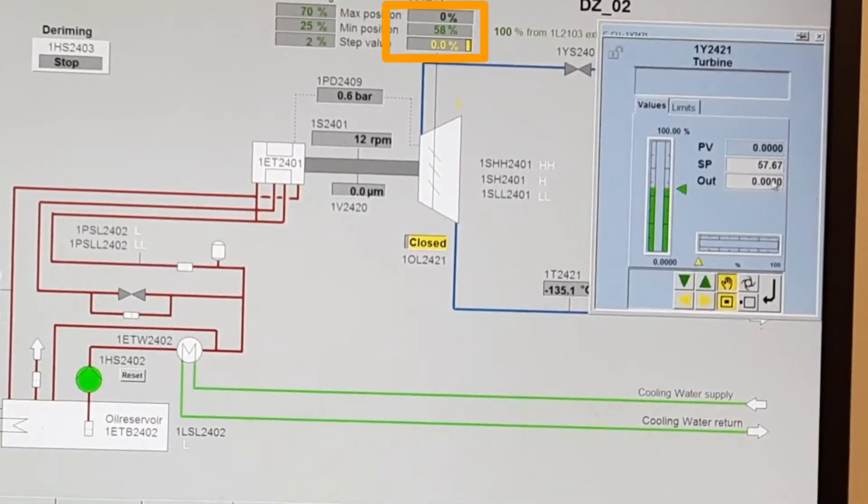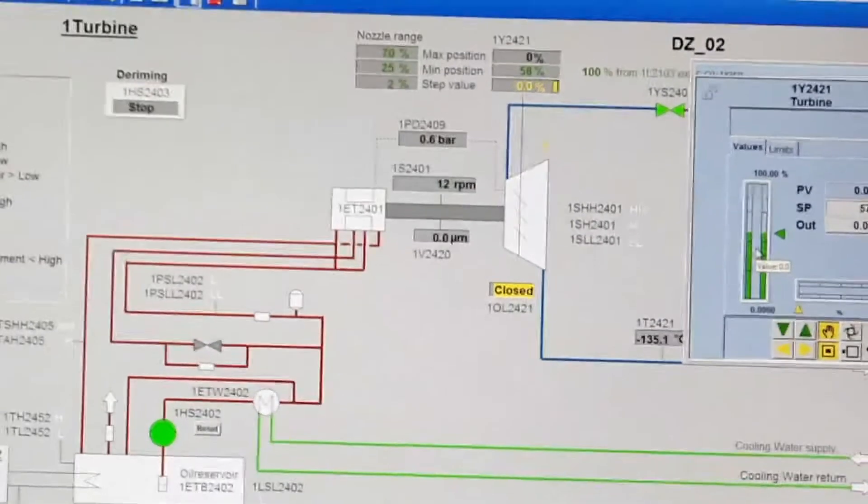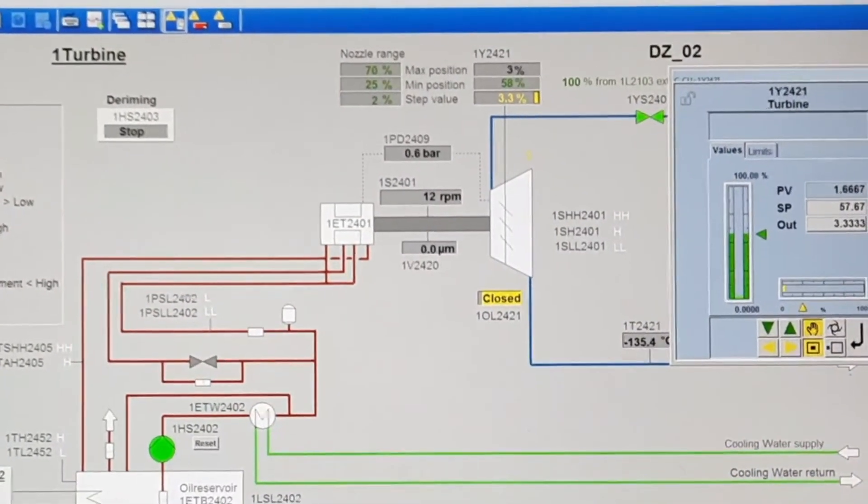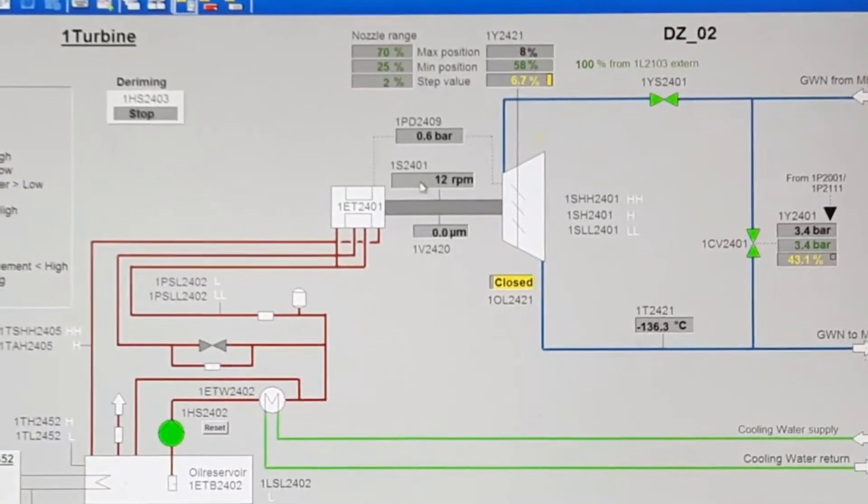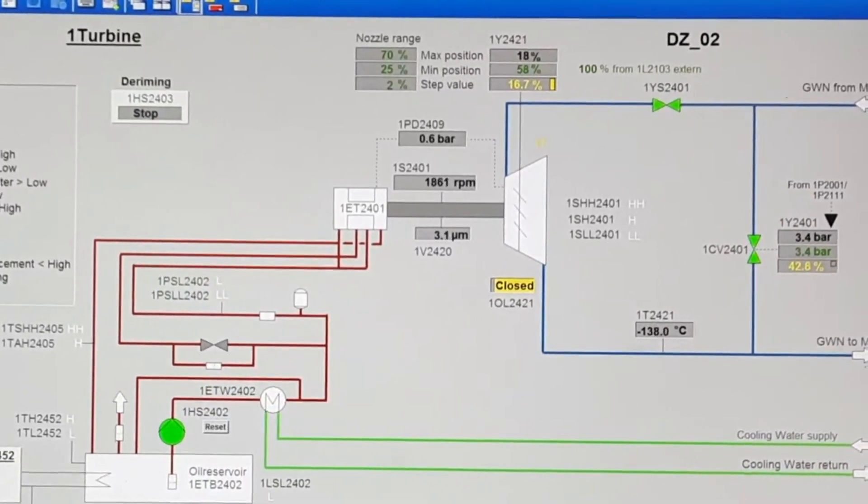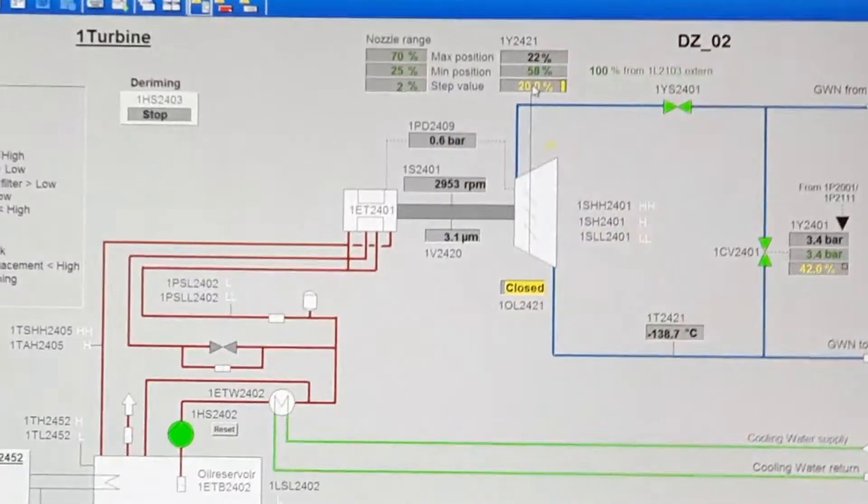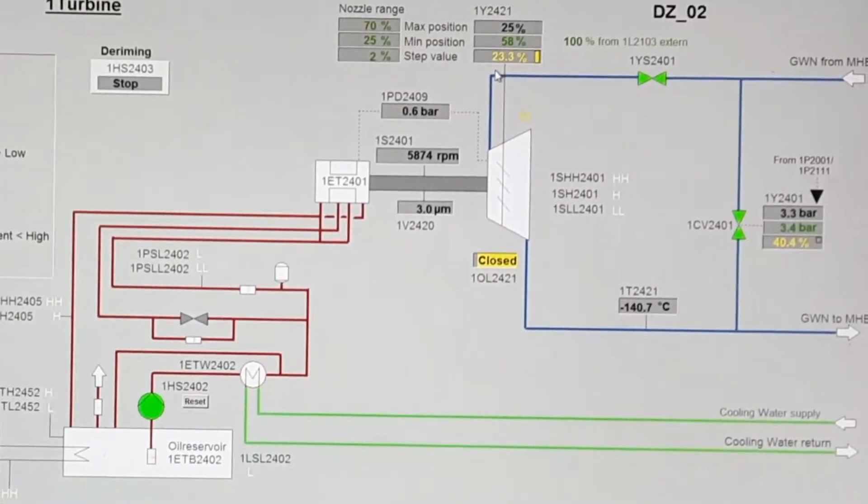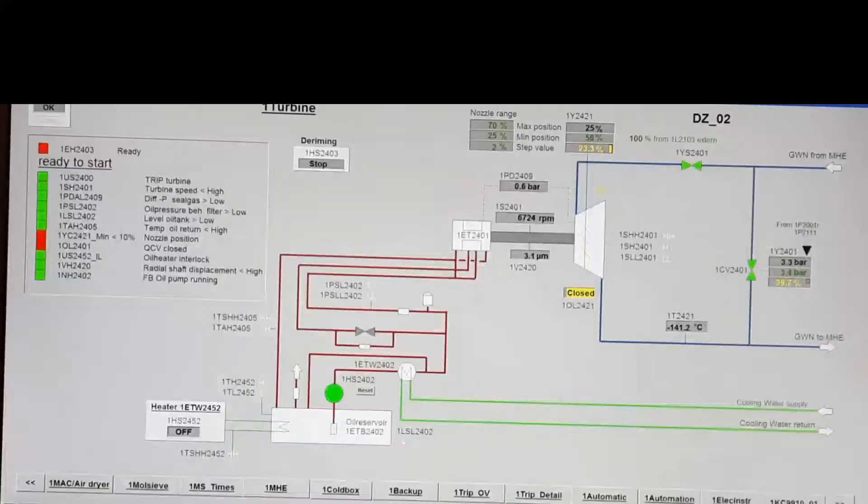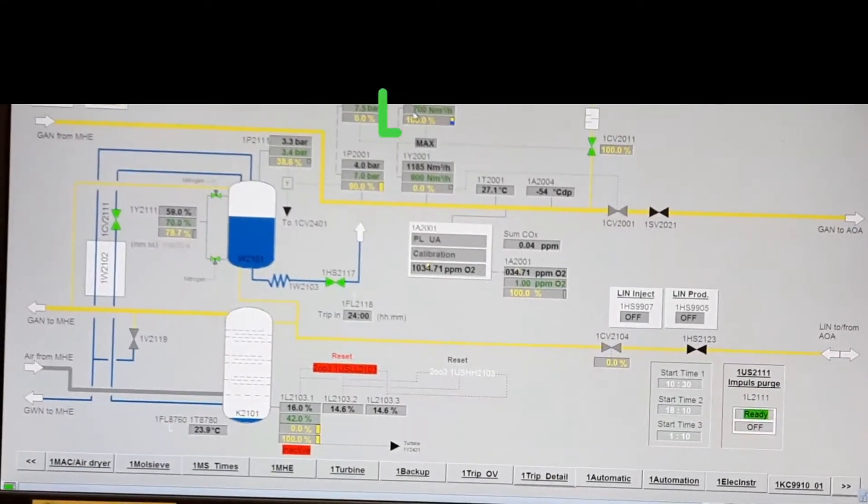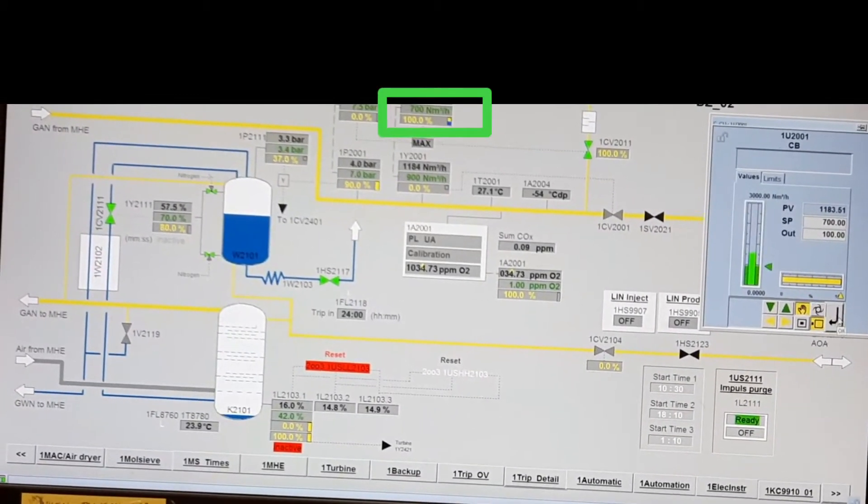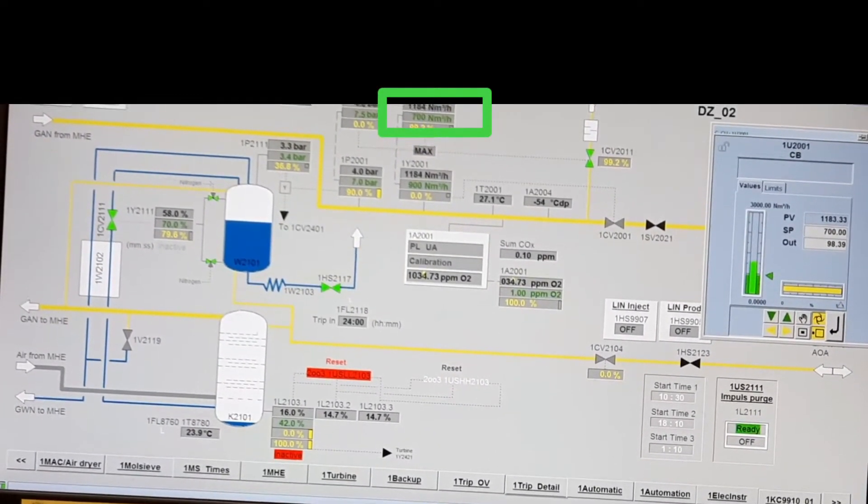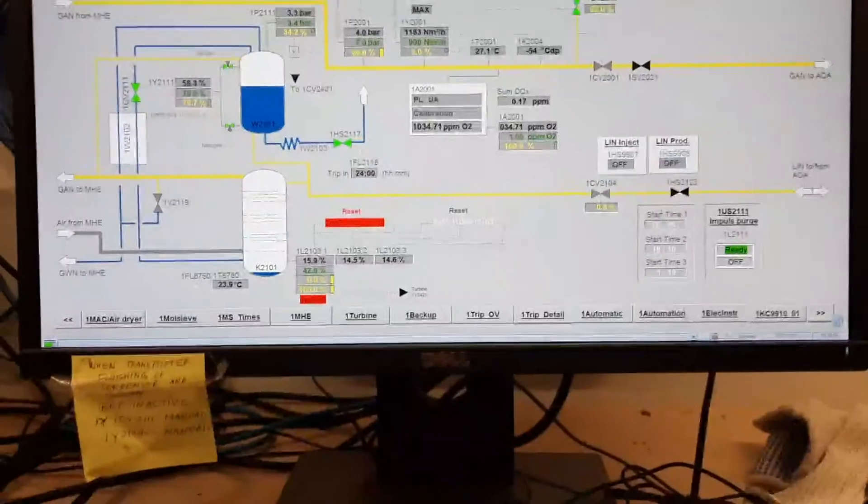Immediately after starting, this valve should open to 25 percent. It's at 24, 21, now 25 percent. If this valve doesn't open and RPM doesn't increase, the turbine will trip. 25 percent is already opened. Now go to the cold box and put this one to auto.